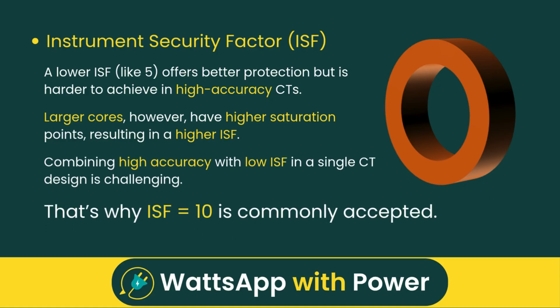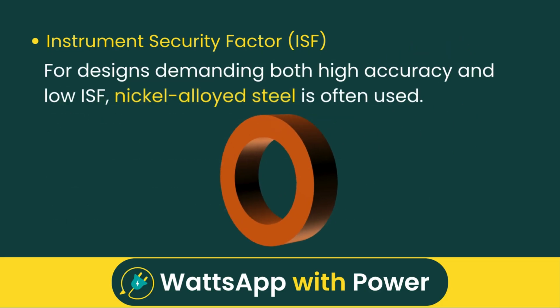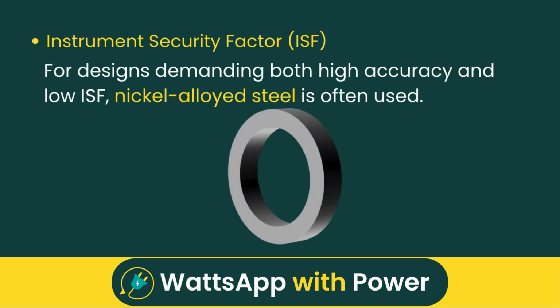That's why ISF 10 is commonly accepted, especially since most modern meters are built to withstand 10 times the rated current for 5 seconds. For designs demanding both high accuracy and low ISF, nickel alloyed steel is often used as core material to meet these performance criteria.